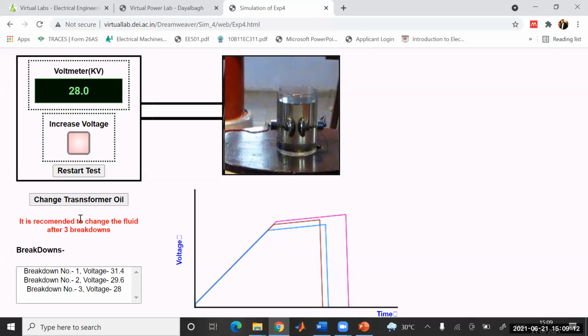Because of this property, if the oil loses that property, there will be a major concern about the insulation, the dielectric breakdown, and other problems. Even carbon deposition occurs with the breakdowns. Whenever there is a breakdown, there's no visible issue on the scene, but the breakdown capacity decreases - it was 28 and now it will be around 26 or so.